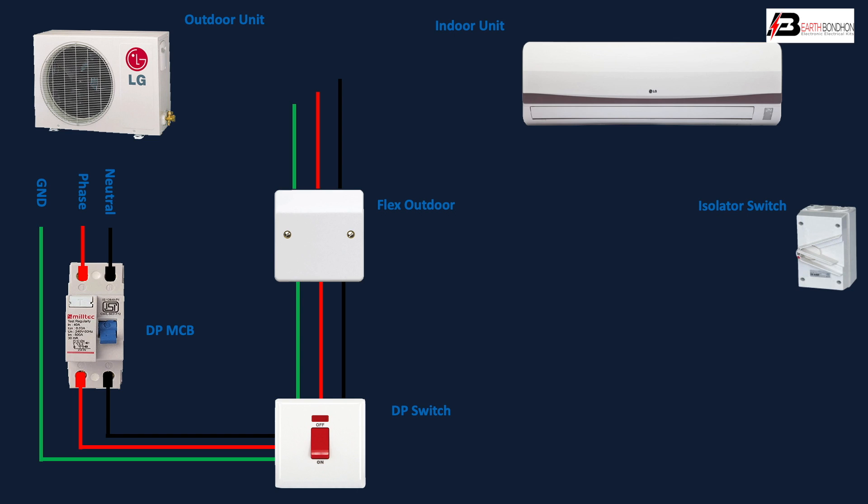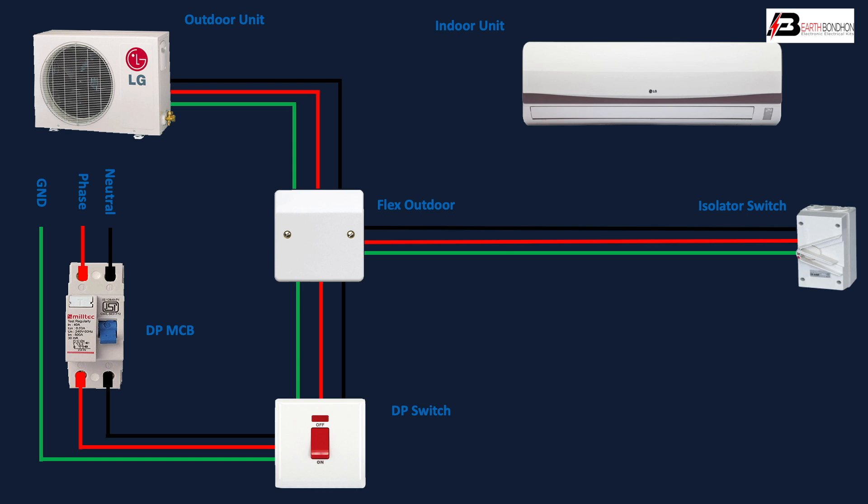For the outdoor unit connection: phase, neutral, and ground — meaning earthing — connect from the flexible outgoing to the isolator input. From the isolator outgoing, connect to the indoor unit — phase, neutral, and earthing. The indoor unit outgoing then connects to the outdoor unit via the control unit.